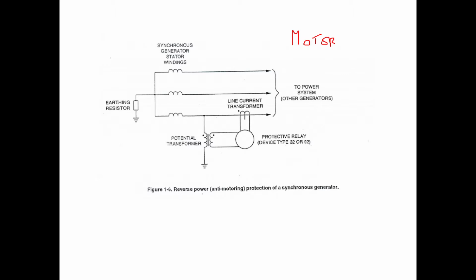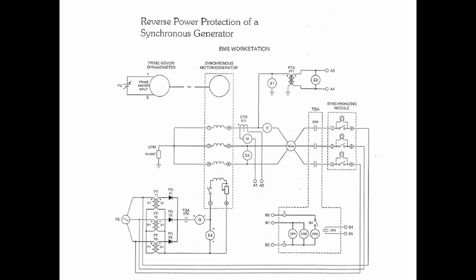So here this is the potential transformer and this is our current transformer. The input to the relay, that is device number 32 or 92, is a directional relay or anti-motoring protection. There are two inputs to this relay. One input comes from the voltage transformer, another input comes from the current transformer, and it measures the angle and direction between the voltage and current, and when the direction reverses, it issues a trip signal to the circuit breaker.